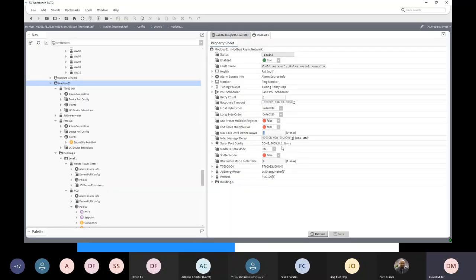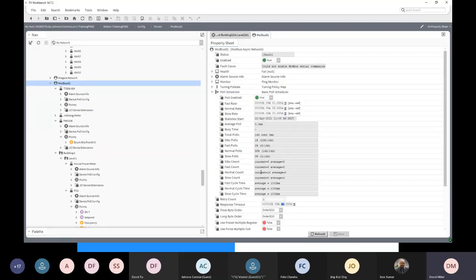Okay, and the response timeout, I'm going to wait 1 second to get the reply back. Okay, if I don't get a reply back in 1 second, I'll try again. Get no reply, I'll now mark the device as down. Okay, and then somewhere else in here there is another poll scheduler that says, where is it?